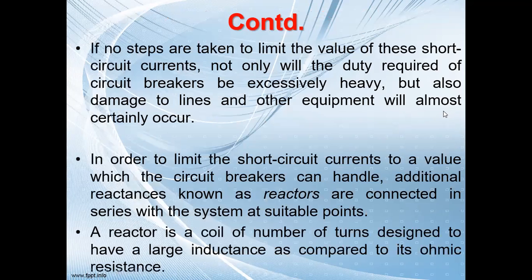So if no steps are taken to limit the value of these short circuit currents, not only will the duty required of circuit breakers be excessively heavy, but also damage to the lines and other equipments will almost certainly occur. So, as we have just discussed, in order to limit the short circuit currents to a value which the circuit breakers can handle, additional reactances known as reactors are connected in series with the system at suitable points. A reactor is a coil of a number of turns designed to have a large inductance as compared to its ohmic resistance. So it is basically an inductor.